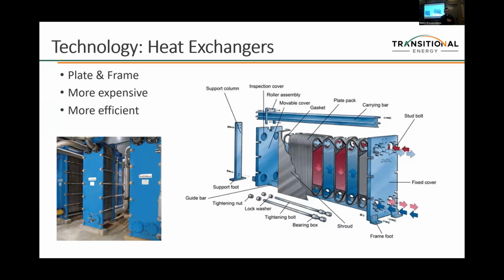A picture of these heat exchangers is on the left. These things can be as tall as this room and however long they need to be, or they can be fairly short. They can be rated to 500 PSI to work with flowback, or 50 PSI for a very low pressure system. Plate and frame tends to be more efficient, but also more expensive, particularly if the chemistry of the fluids means the metallurgy has to be very specific so that scaling isn't a problem.